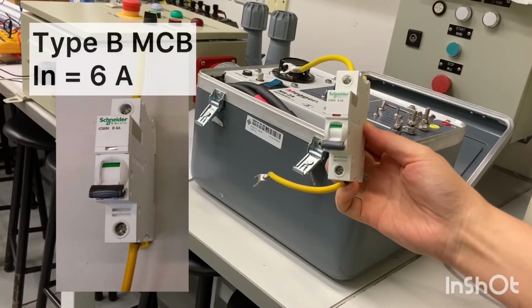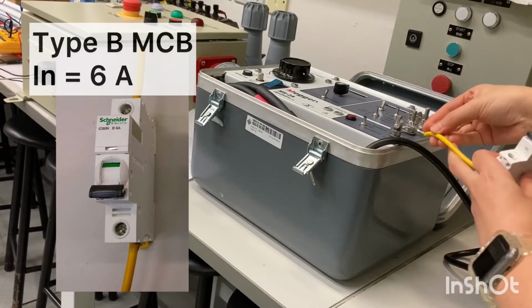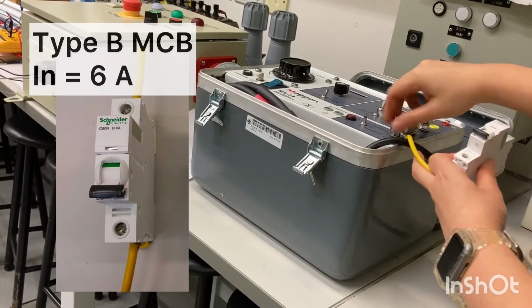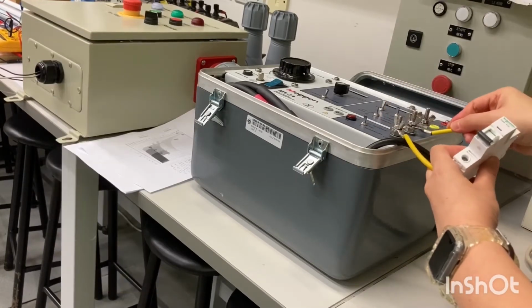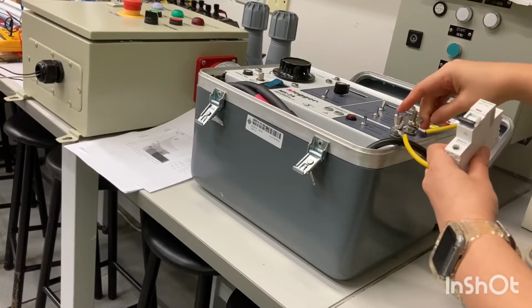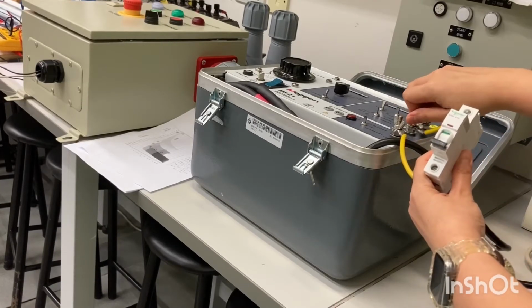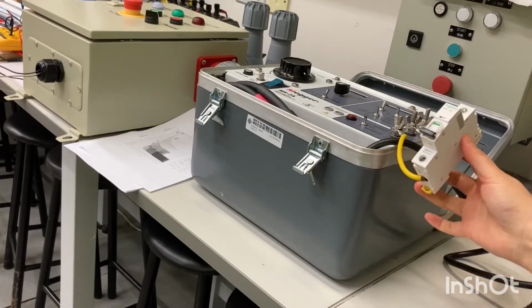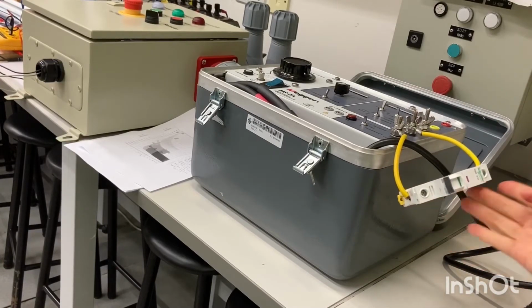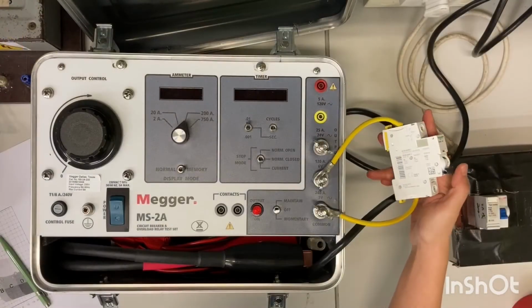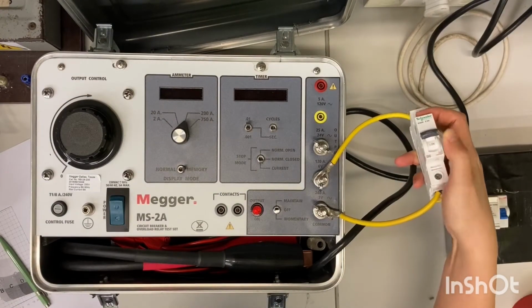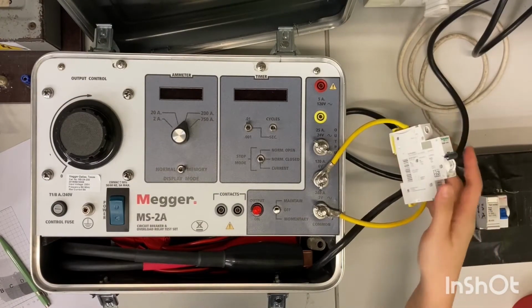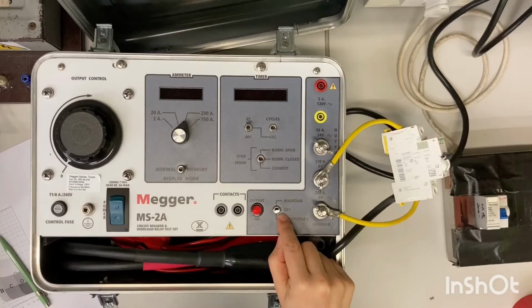The first circuit breaker we are going to test is the type B rating 6 amp MCB. So first of all, we connect the two ends of the MCB to the terminals of the Megger test set. We turn on the MCB. This button should be at the off position before we turn on the Megger test set.